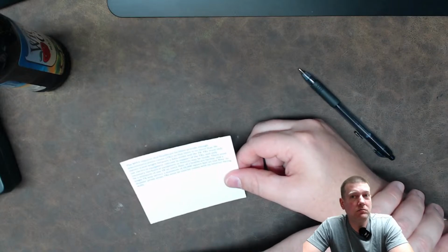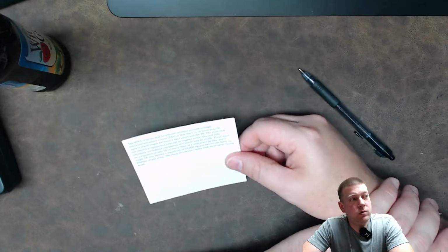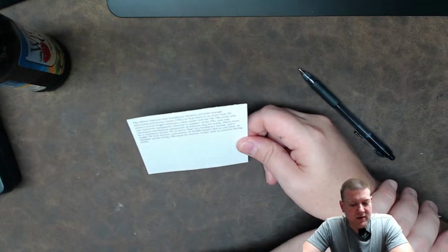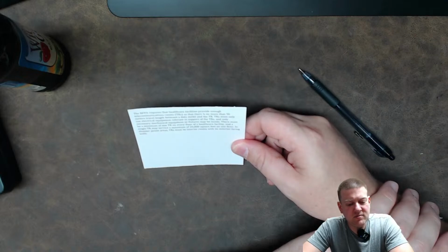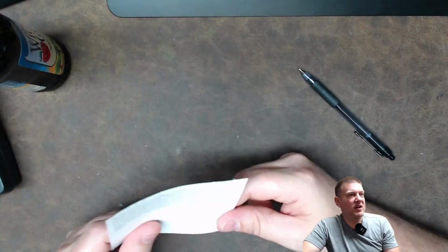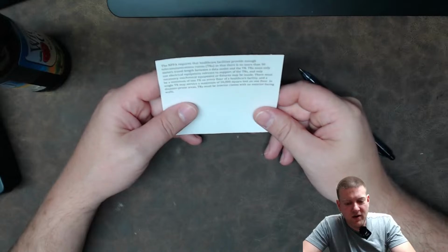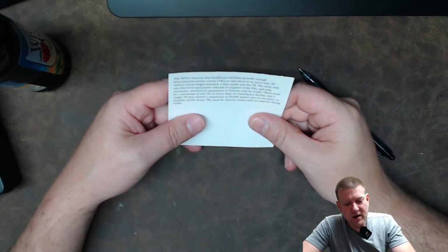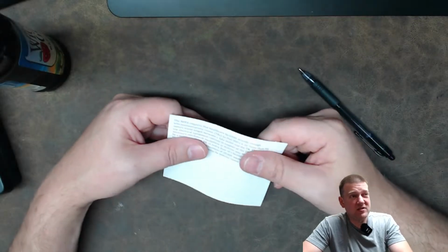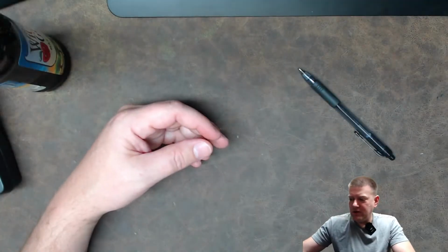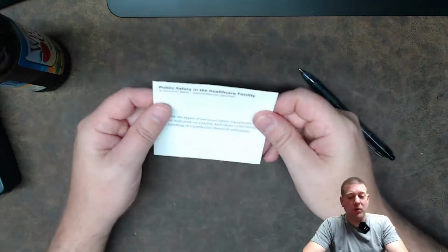And a single TR may service a maximum of 20,000 square feet on any floor. 20,000 square feet. It seems like it's a lot, but I bet you it's not when you're talking a whole bunch of rooms. Okay. In disaster-prone areas, TRs must be interior rooms with no exterior facing walls. No, that's pretty much everywhere, right? Disaster-prone areas. Okay. So the two things that I took out of this card are one on every single floor, and I have to remember that the maximum that they can service is 20,000 square feet. Good to know. I imagine that those numbers are going to be important.